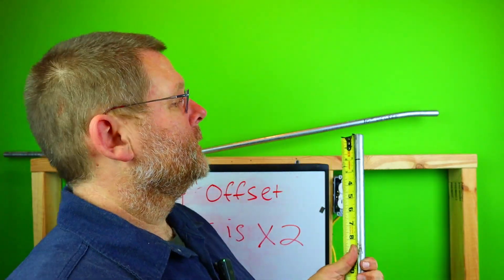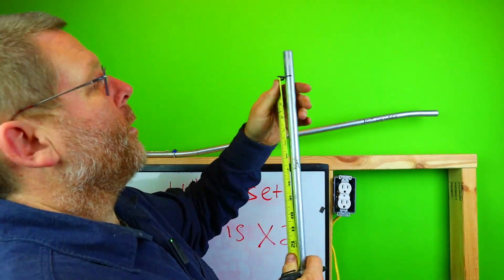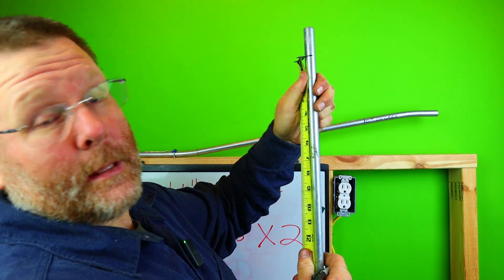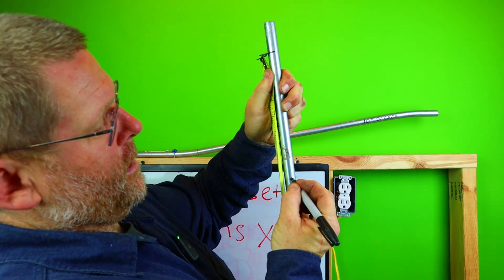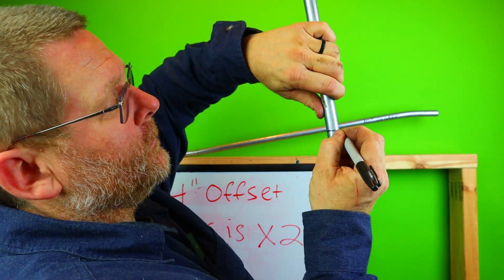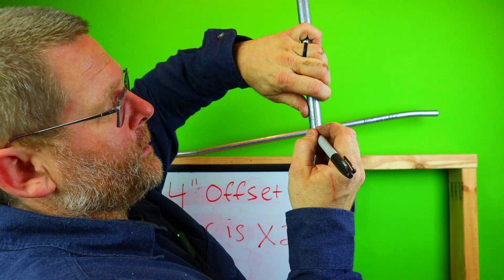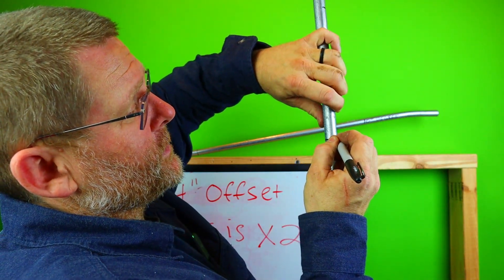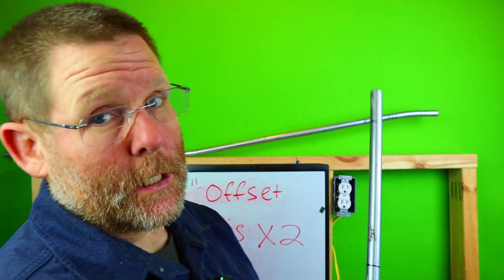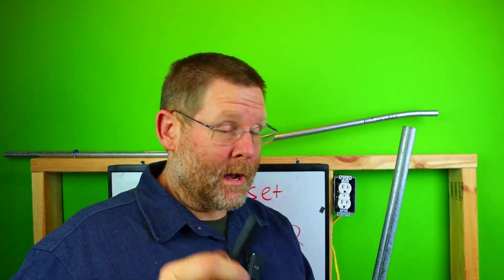Since you remembered, think about subscribing. We have a 4-inch offset, the multiplier is 2, so 4 times 2 is 8. We're gonna put our tape measure right here at the end of the mark and put our other mark at 8 inches. We're gonna go around in a circle. You'd want to treat every job and every piece of conduit like it is the Taj Mahal.